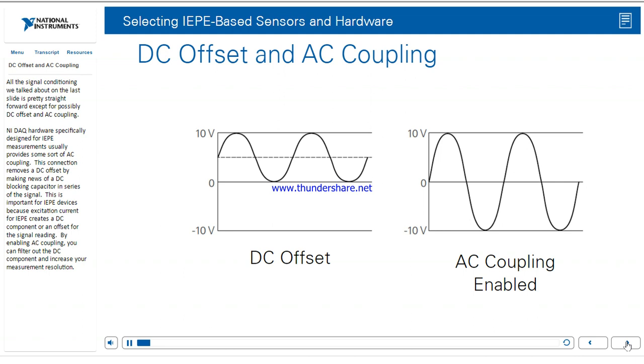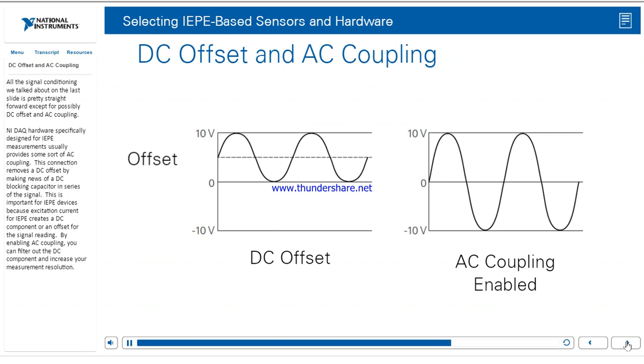All of the signal conditioning discussed is straightforward except possibly DC offset and AC coupling. NI DAQ hardware specifically designed for IEPE measurements usually provides some sort of AC coupling. This connection removes a DC offset by making use of a DC blocking capacitor in series with the signal. This is important for IEPE devices because the excitation current creates a DC component or offset for the signal reading. By enabling AC coupling, you can filter out the DC component and increase your measurement resolution.